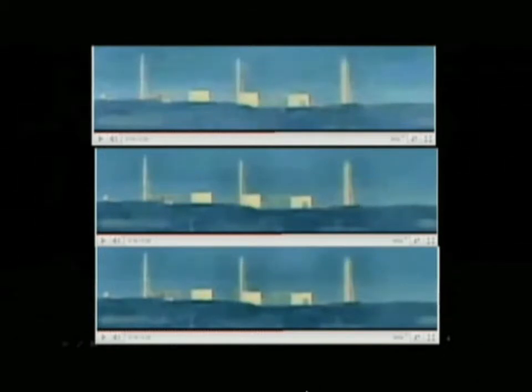This is not supposed to happen. This is a detonation shockwave created by that hydrogen that destroyed the containment structure at Daiichi Unit 3.